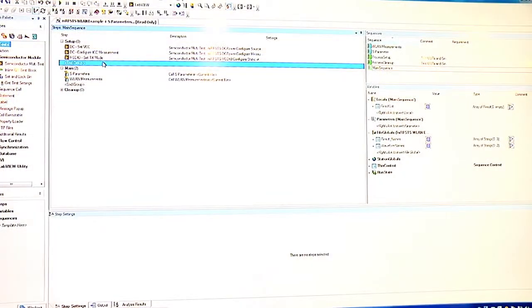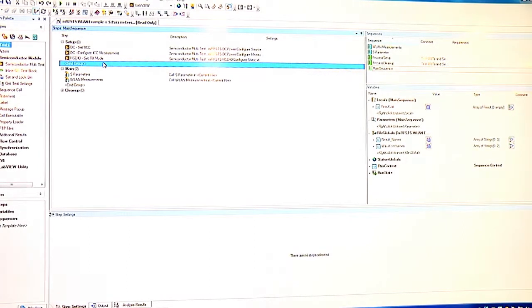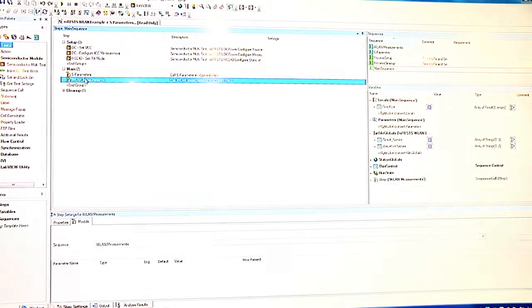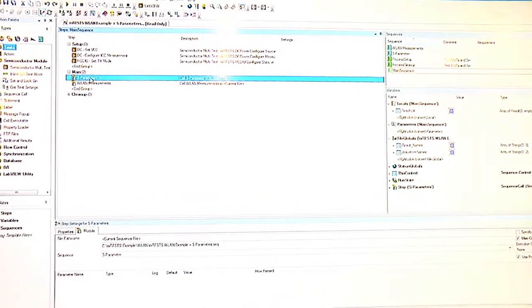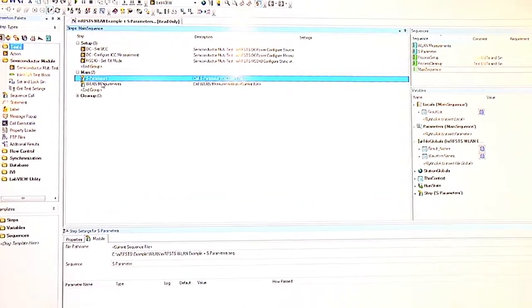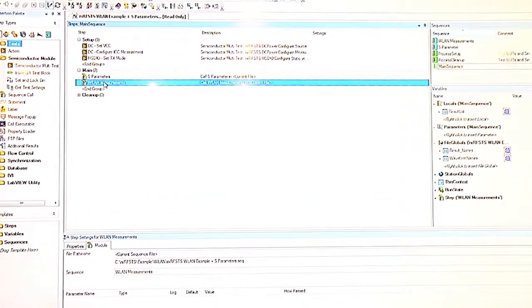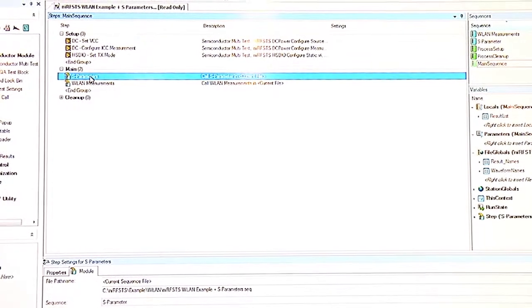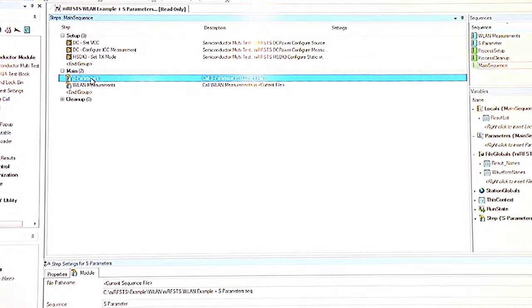Here we can see NI TestStand with LabVIEW code modules. We have two sub-sequences: one for doing S-parameter measurements and one for doing WLAN measurements. These S-parameter measurements were enabled by that RF port module we saw in the hardware earlier.